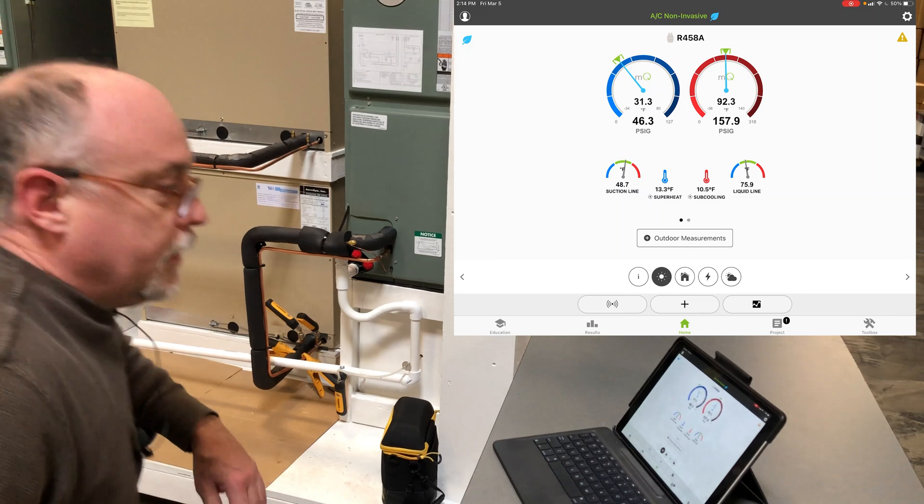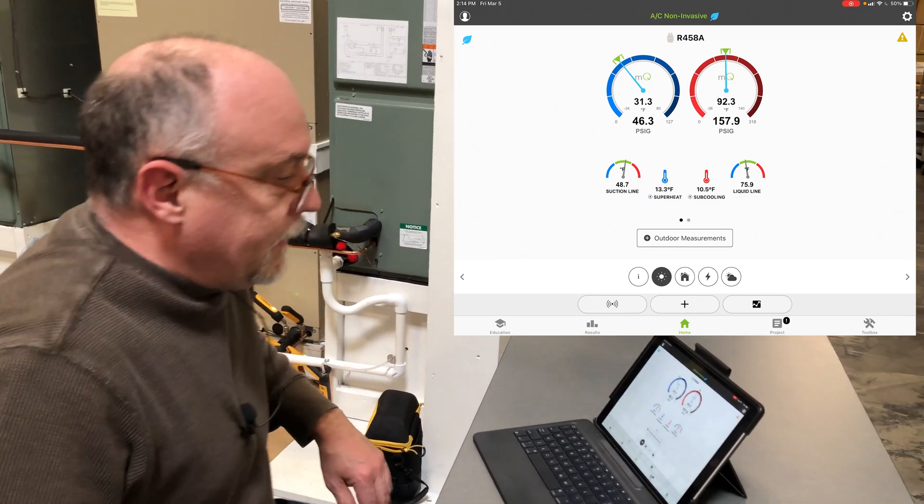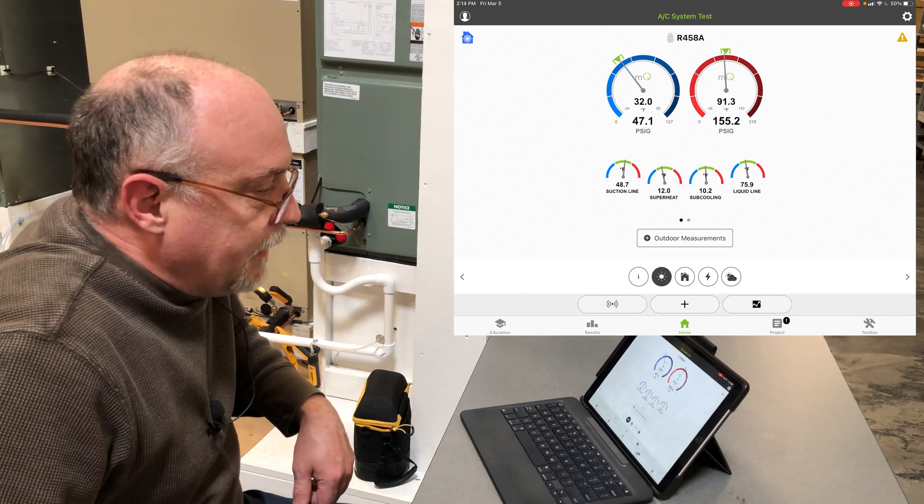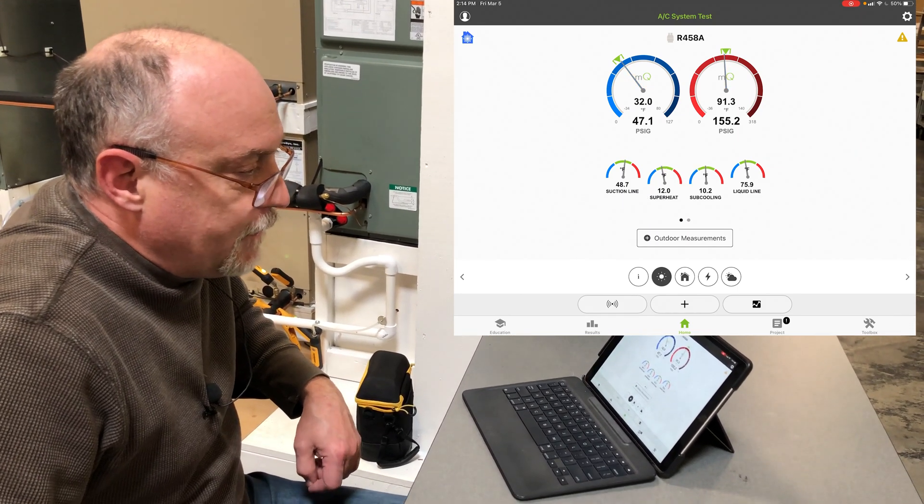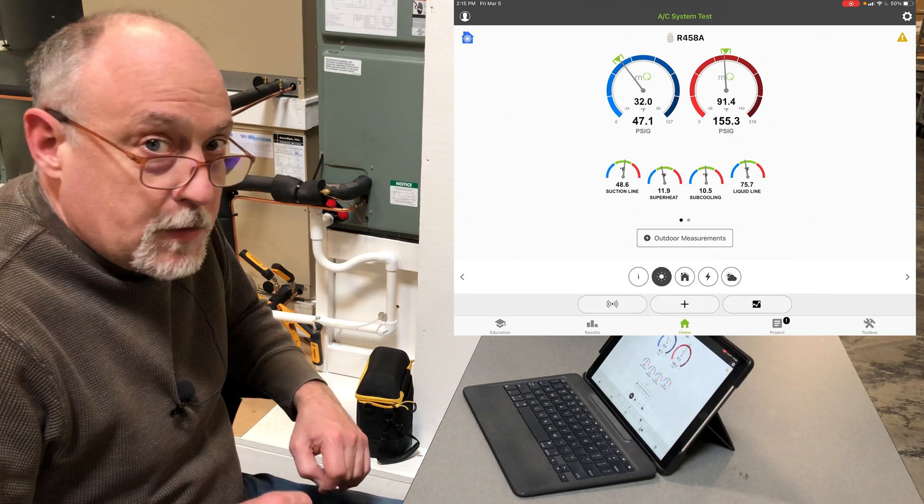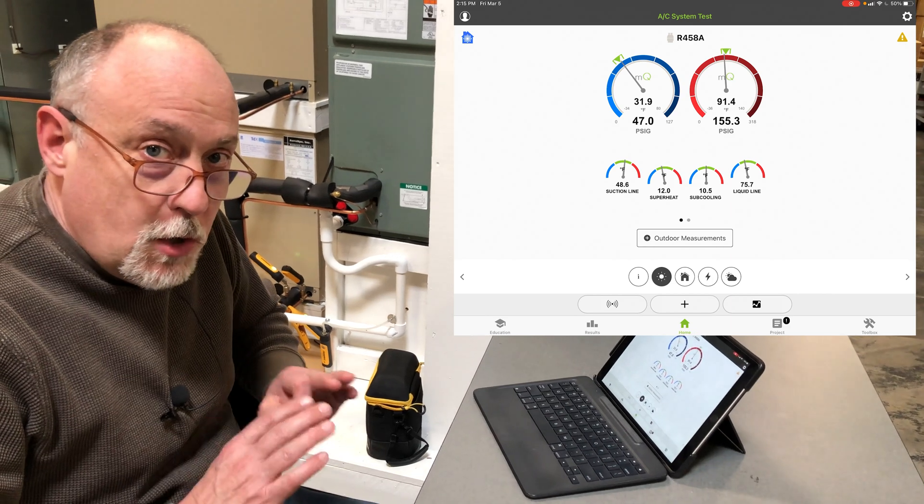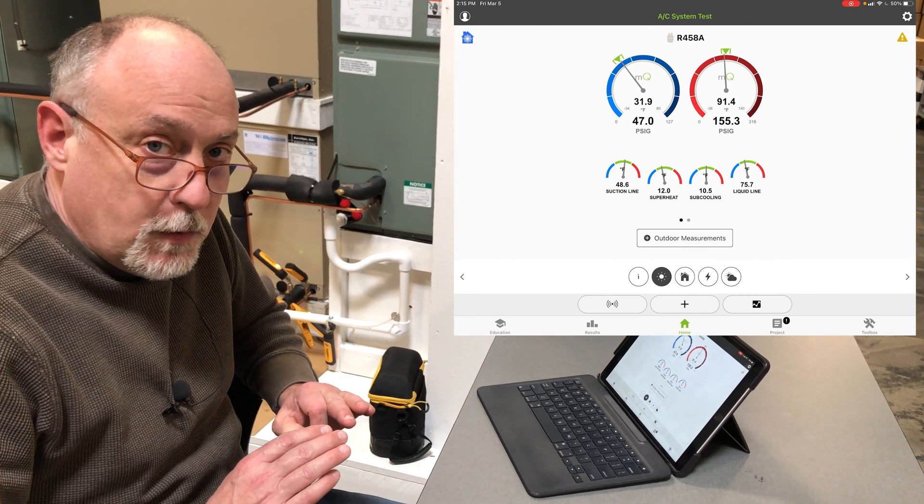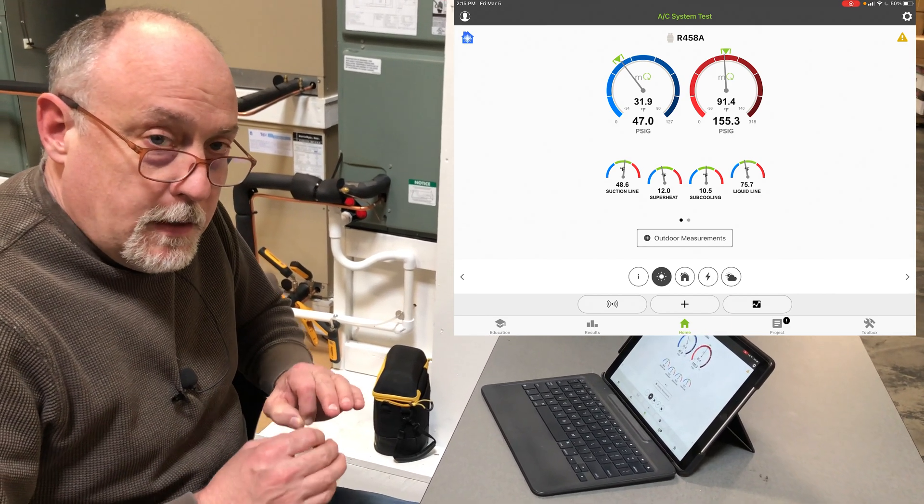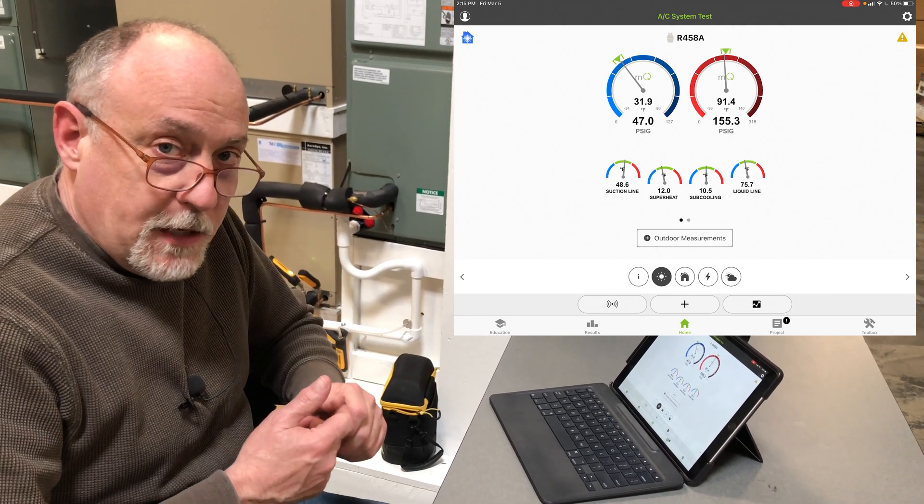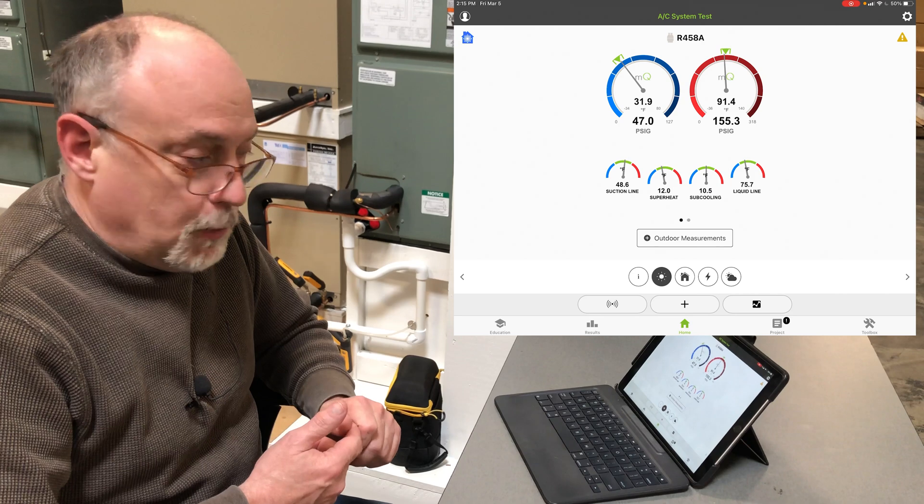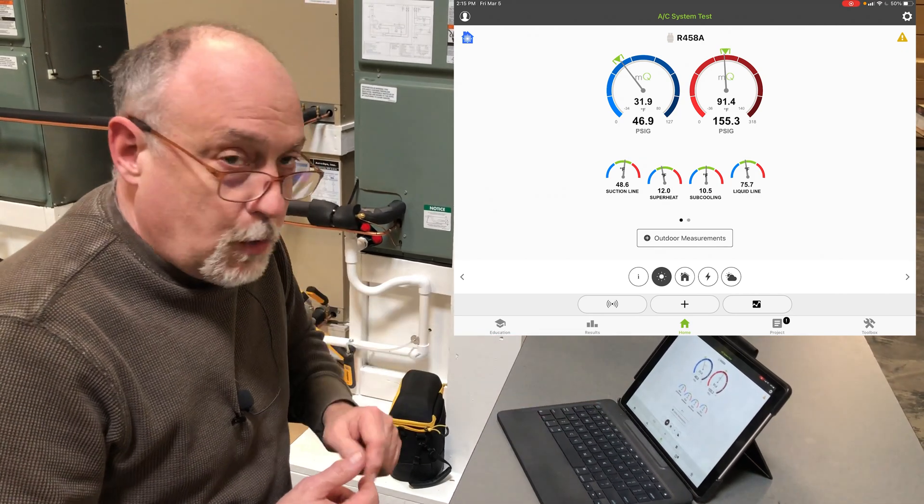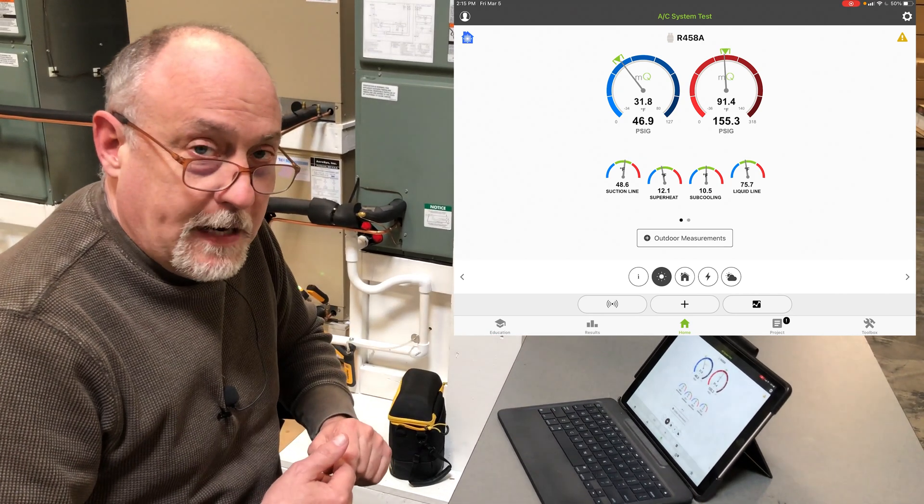They're blue now, and you'll see 46, 157, and it just went 47 and 155. You can see almost no change when it went from the estimated pressure to the actual pressure, and now our actual superheat is 12 and 18.5.